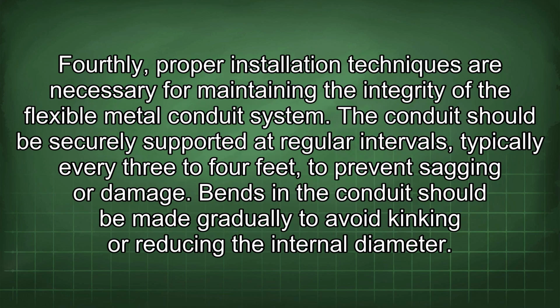Fourthly, proper installation techniques are necessary for maintaining the integrity of the flexible metal conduit system. The conduit should be securely supported at regular intervals, typically every 3 to 4 feet, to prevent sagging or damage. Bends in the conduit should be made gradually to avoid kinking or reducing the internal diameter.